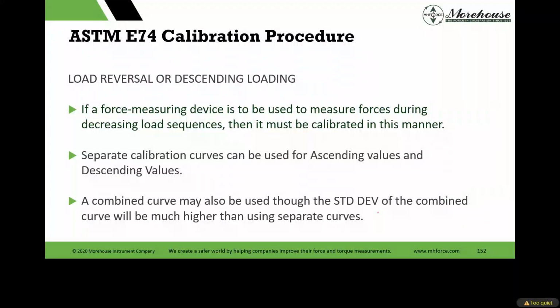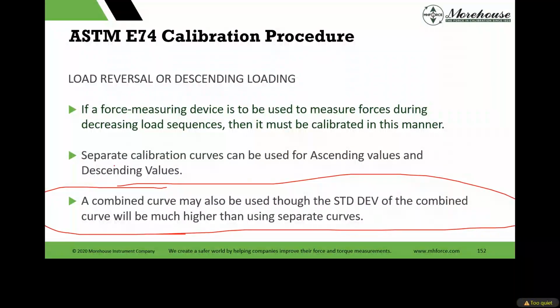So E74 is descriptive. That basically says if a force measuring device is to be used to measure forces during decrease, then it must be calibrated in that manner. It says separate curves should be developed. And then I say E74 mentions nowhere about doing this. This is industry needs something for this.